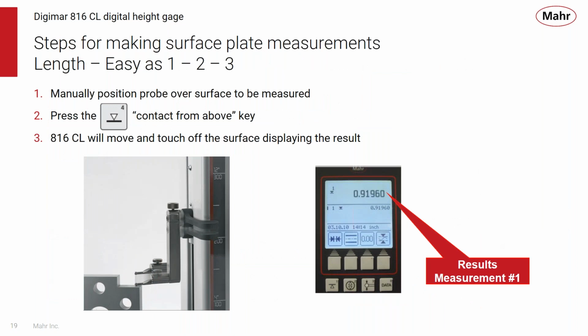And making a surface plate measurement for length with the 816 is easy as 1, 2, 3. All you have to do is manually position the probe over the surface that you're going to measure, press the down contact from above key, and then the 816, using its motorized drive, will move down and touch off on the surface, displaying your results. The results are displayed in an easy to read, large lit display, easy for the operator to make measurements simply using the one key. So you position over the part, press the down measurement key, and the 816 will take over and make that measurement for you.